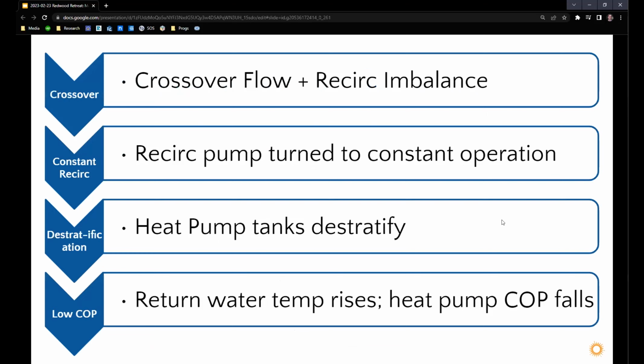We learned a lot of lessons about crossover flow and recirculation imbalance. So one of the things with old multifamily is this thing called crossover. We like to think of hot and cold water systems as separated from each other, but in reality, there's a very thin line that separates them, and that's often a single lever shower valve in every single apartment and other places in the apartment too. And when the gaskets inside of those places fail, if there's a pressure difference, if cold is at a higher pressure than hot, then the cold will flow over into the hot water system, and wherever that crossover is happening, the next unit over will experience colder hot water than they would like.